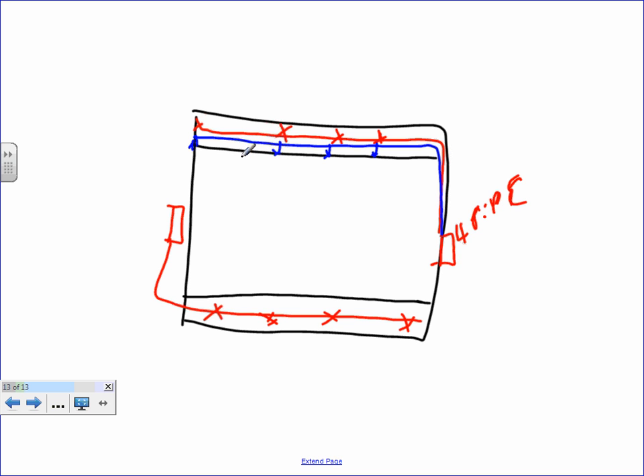Now, if the alarm system is not required because it has sprinklers, do you still have to follow all the rules and pass all the inspections that were required? Yeah. So if you put one in, then it has to be kosher. Yes, if you put one in, it has to be installed to code. Yep. That's a really good question.